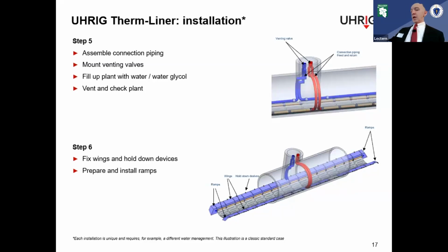So as you can see, the way the water would flow, your supply comes in from the heat exchanger on the street, from the heat exchanger in the building, from your heat pump in the building to your Therm-Liner out on the street, and then returns back to the heat pump, in heating season with energy, in cooling season dumping energy into the sewer water.